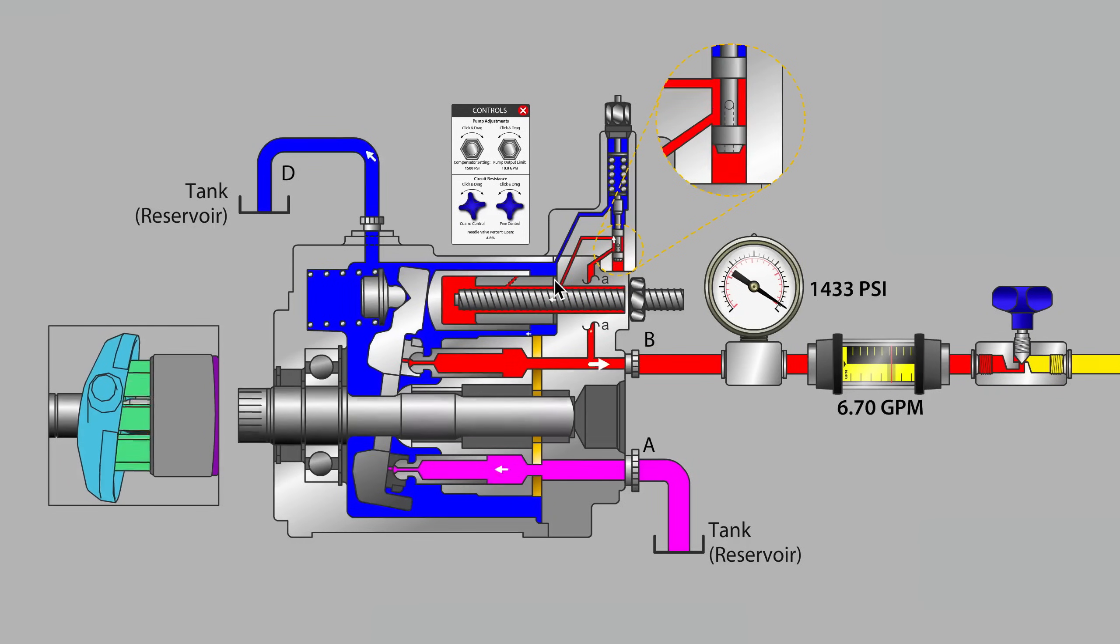Well when the pump is in the mode where it is pressure compensating, outlet fluid is being pushed into the control piston, but when the pump is coming back on stroke, oil that was in the control piston has to be ejected.